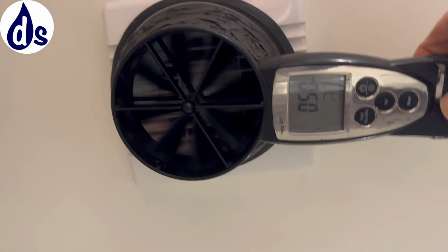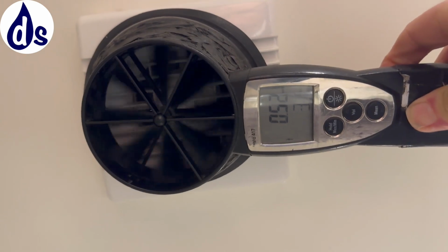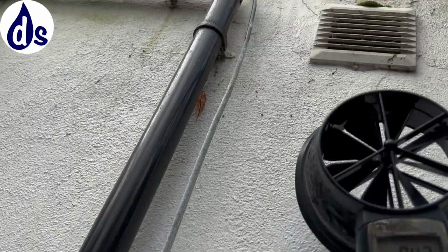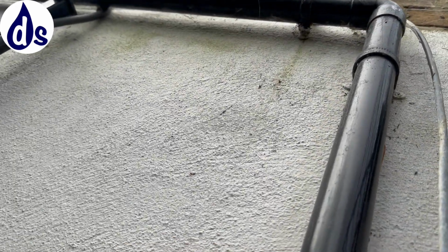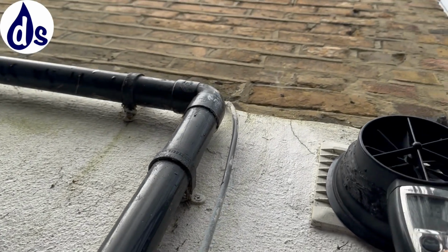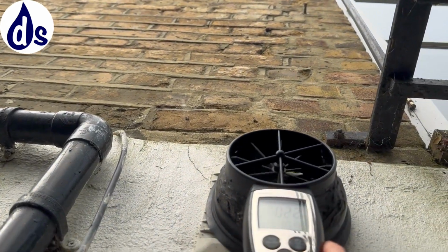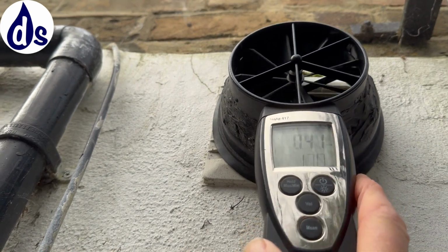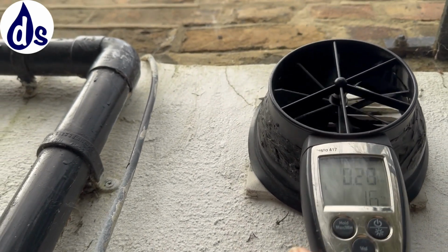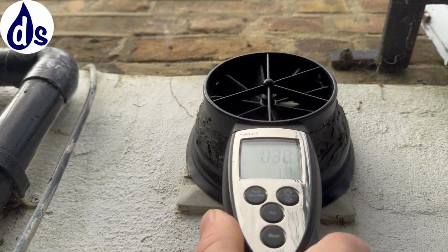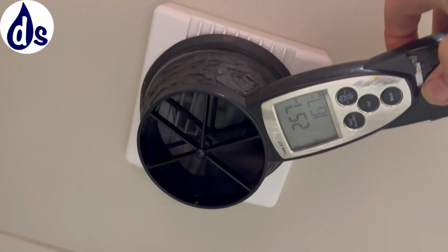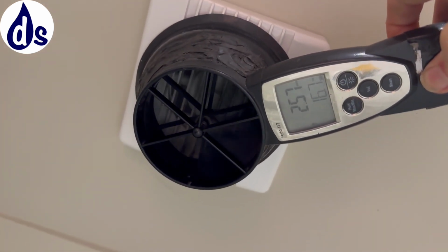I measured the vent speeds in both bathrooms using an anemometer and discovered that one of the vents wasn't going out at all. That was the main bathroom that's used, and you'll see here that there's more or less no airflow coming out. It often happens that builders don't connect the vents to the outside. It takes a lot of effort and very few people ever check it.